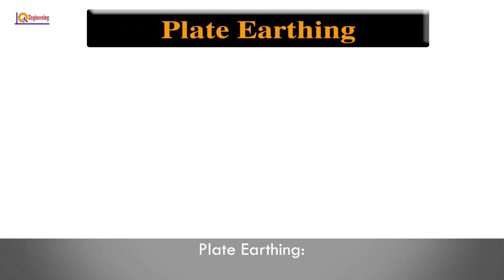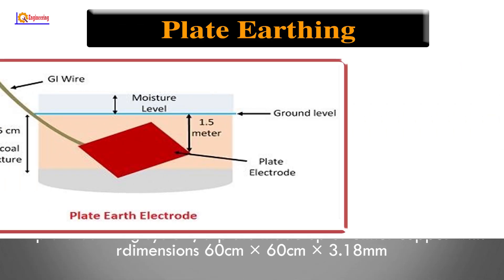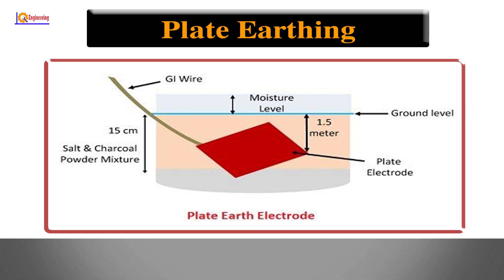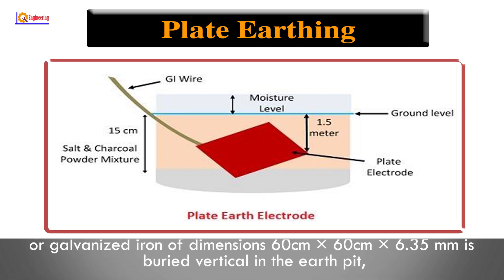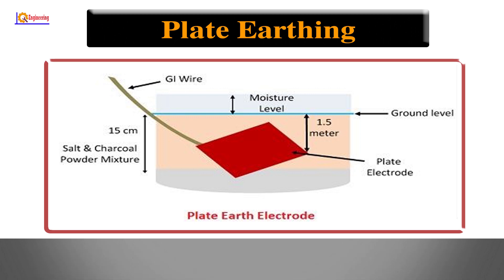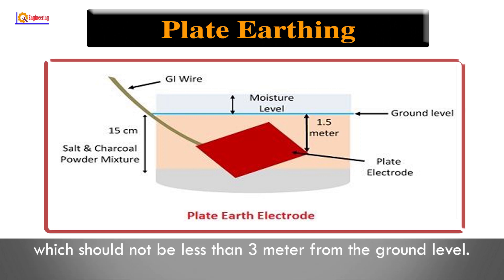Plate earthing: In the plate earthing system, a plate made up of either copper with dimensions 60 cm x 60 cm x 3.18 mm, or galvanized iron with dimensions 60 cm x 60 cm x 6.35 mm, is buried vertically in an earth pit which should not be less than 3 meters from the ground level.